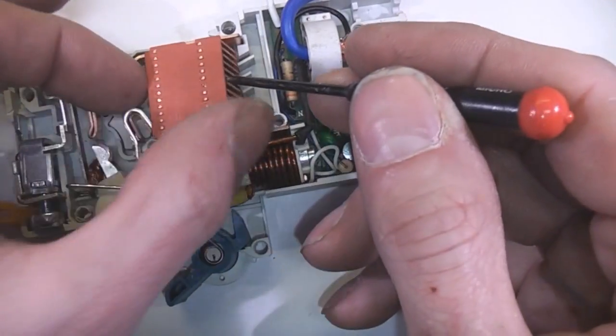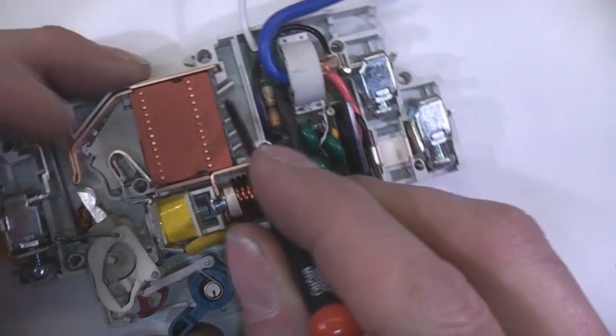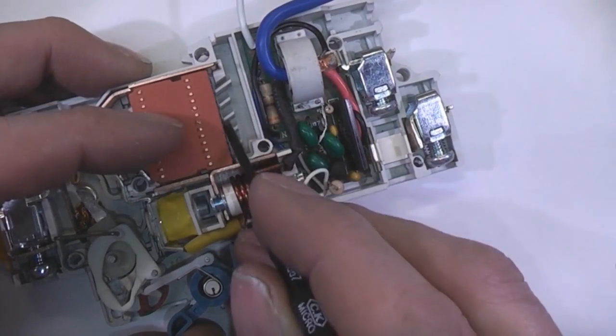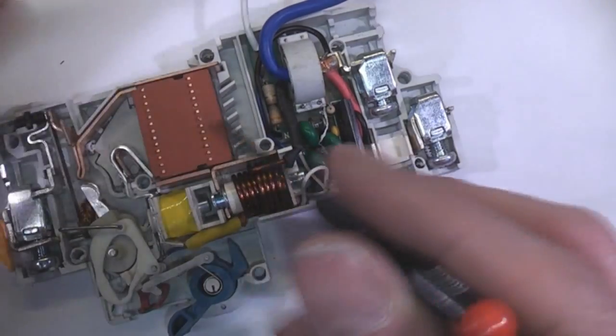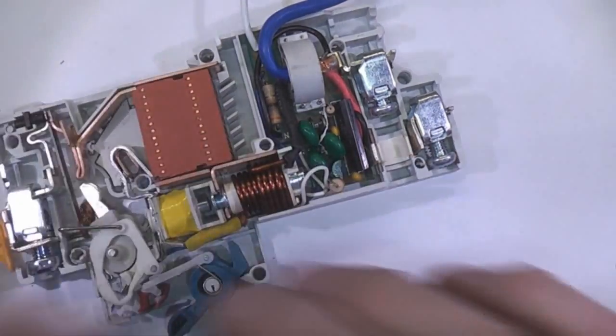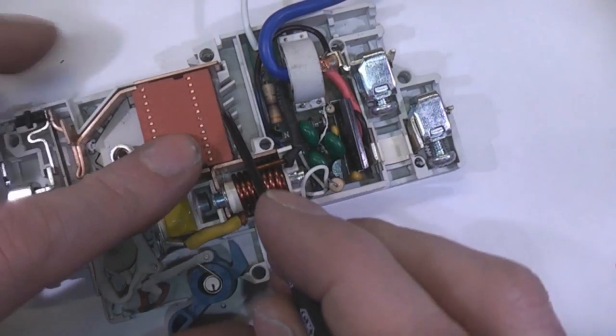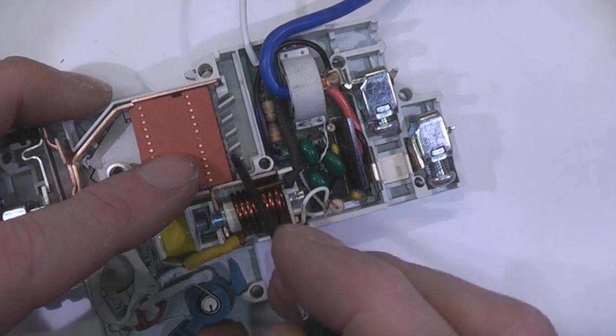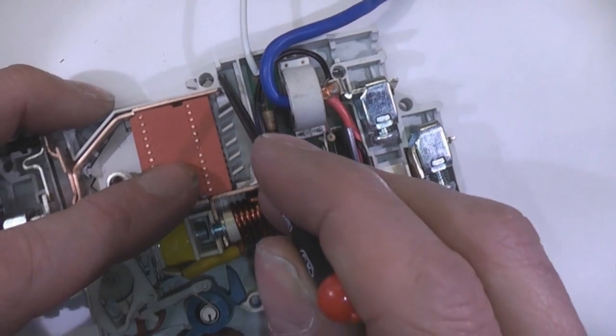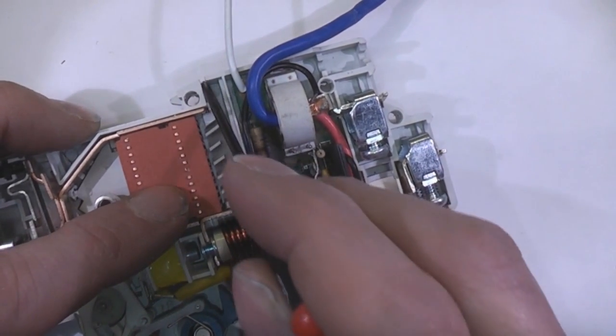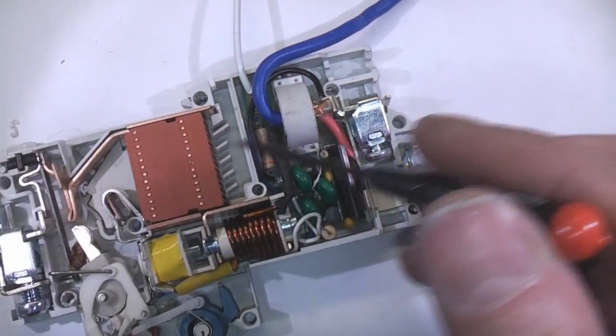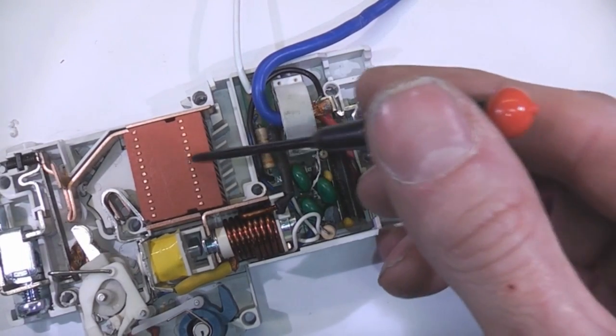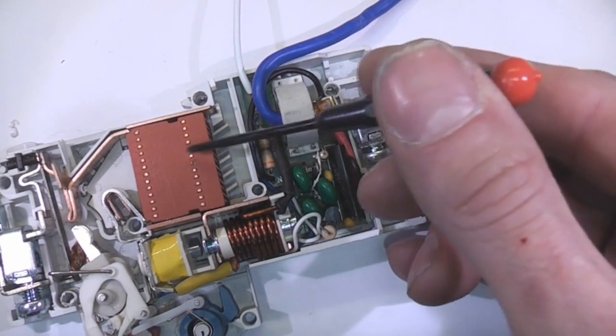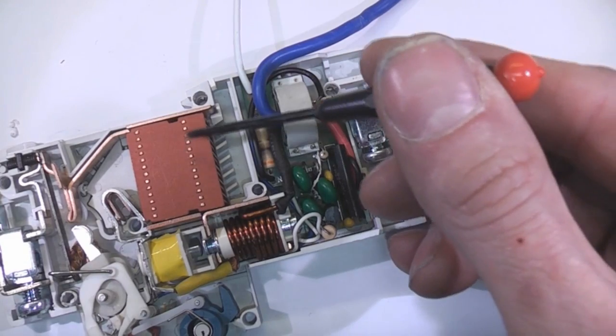But you'll notice that over here we've got these horizontal pieces, and these are actually a vent, so that in the worst case we get just some colossal amount of energy arcing over in here, instead of the whole thing just catching fire and exploding, it actually directs that blast down these slots here and out to this hole in the back. So this is basically a phenomenon known as arc flash, which can actually be very dangerous. People on large switchboards, a really bad arc flash can actually be fatal. People have actually died from it.